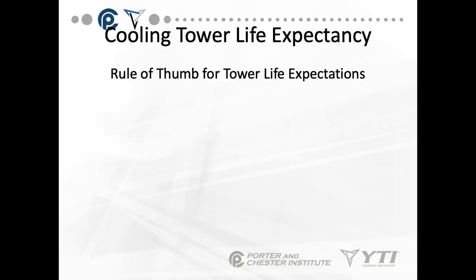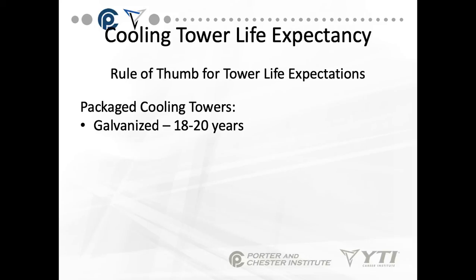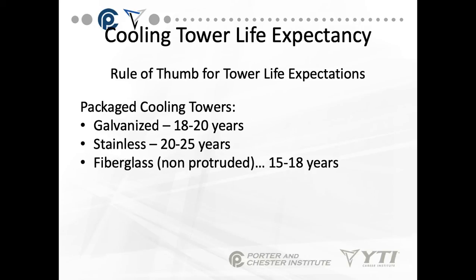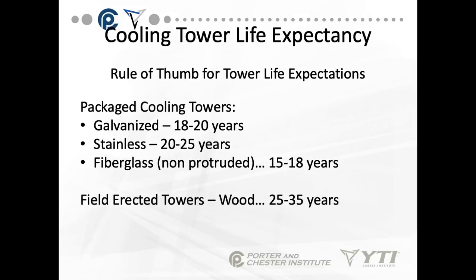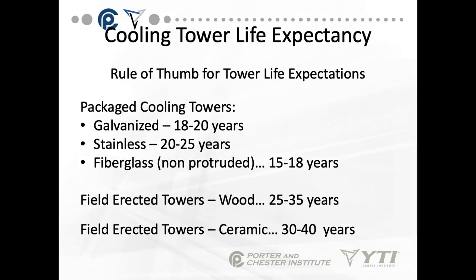With proper maintenance, most cooling towers will last, if they're packaged cooling towers, for about 18 to 20 years. Made out of galvanized. Stainless steel, 20 to 25 years. Fiberglass, 15 to 18 years. Field erected towers, if they're wood, 25 to 35 years. And ceramic, 30 to 40 years. So again, believe it or not, the stuff that's made in the field actually has better life expectancies.